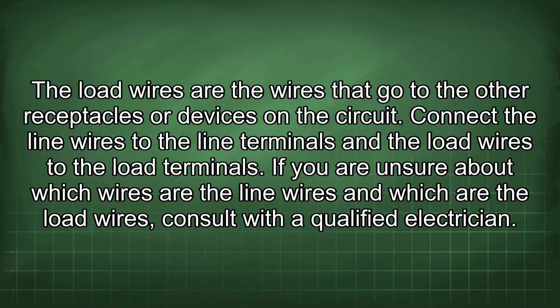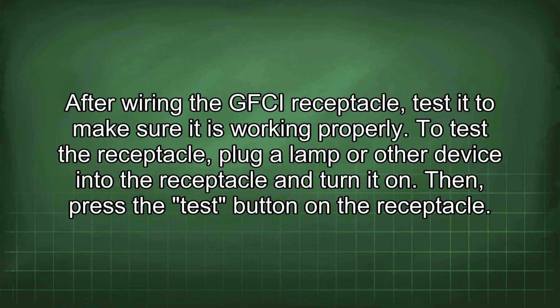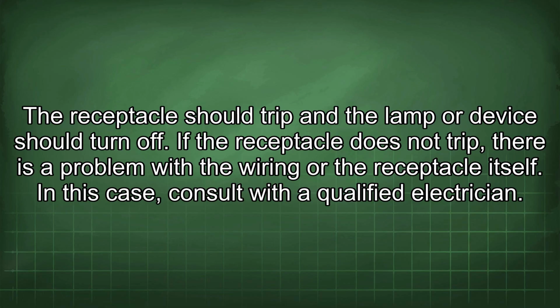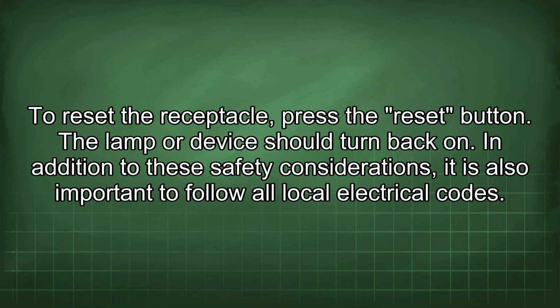After wiring the GFCI receptacle, test it to make sure it is working properly. To test the receptacle, plug a lamp or other device into the receptacle and turn it on. Then press the test button on the receptacle. The receptacle should trip and the lamp or device should turn off. If the receptacle does not trip, there is a problem with the wiring or the receptacle itself. In this case, consult with a qualified electrician. To reset the receptacle, press the reset button. The lamp or device should turn back on.